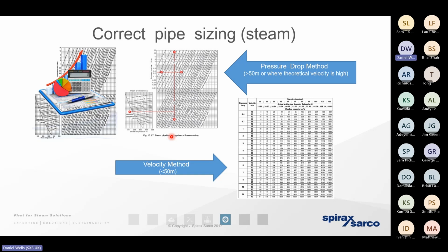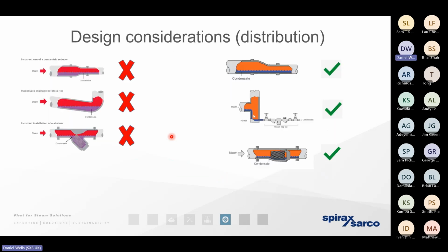The reality is the vast majority of design engineers are simply not going to know what condition is going to exist, because it varies, it changes throughout the day. So the safe spot is probably sizing at around 25 meters per second velocity. That way we can have peace of mind that we shouldn't have too many problems with an excess of erosion as a result of that poor quality steam. So we need to get that condensate out of the infrastructure very, very quickly.